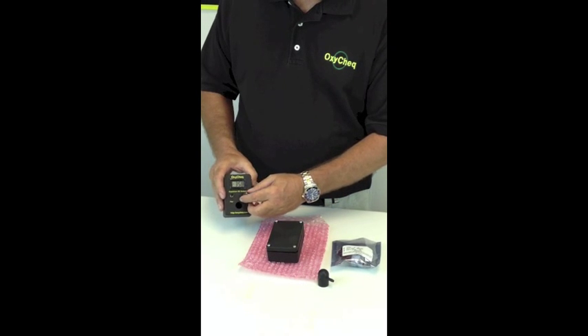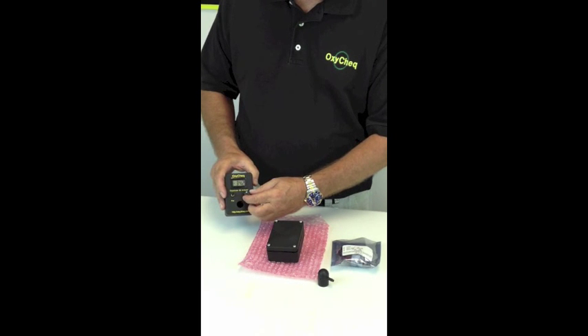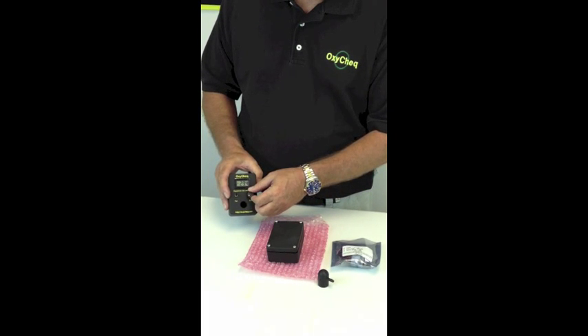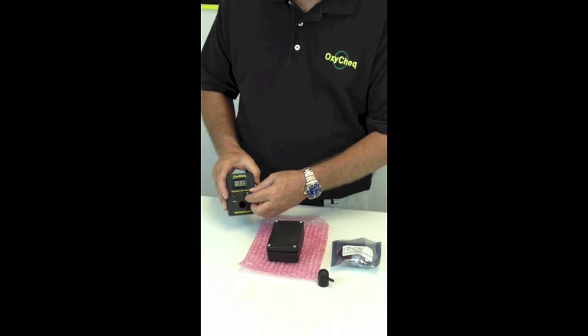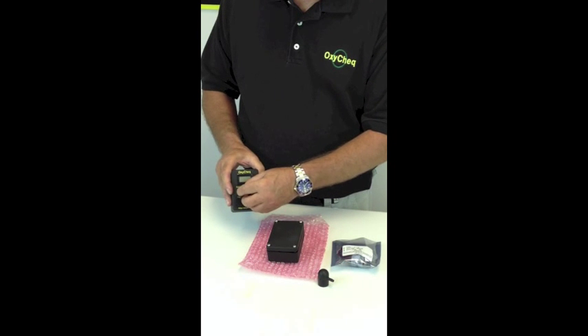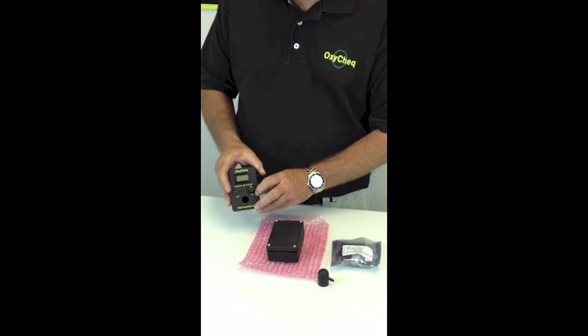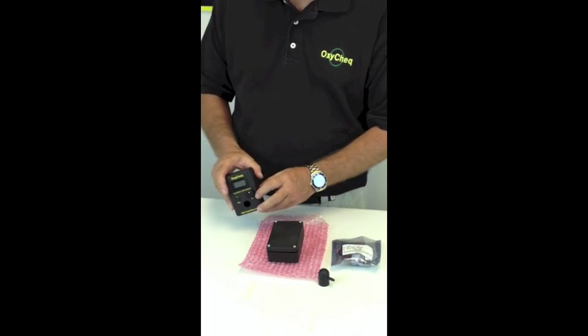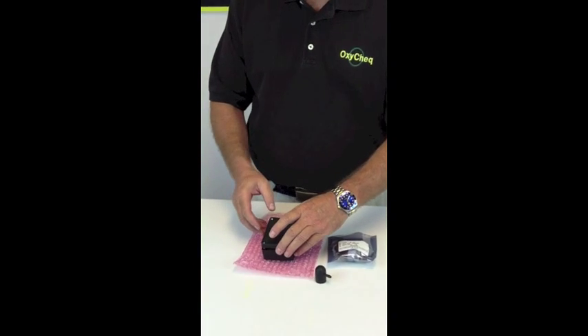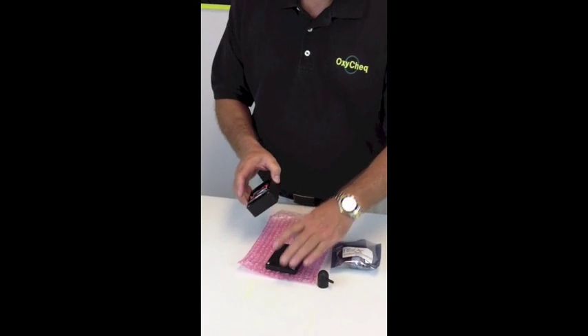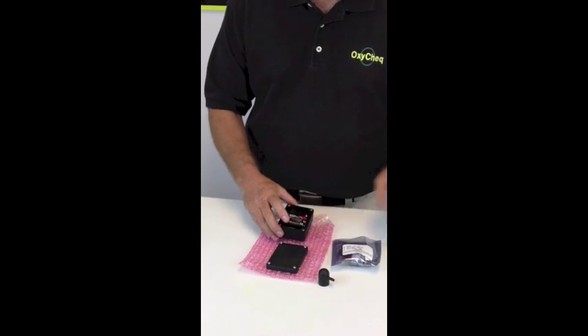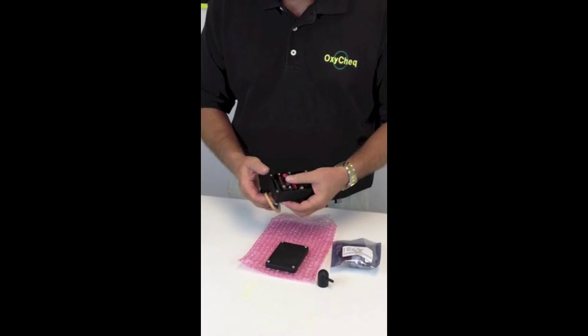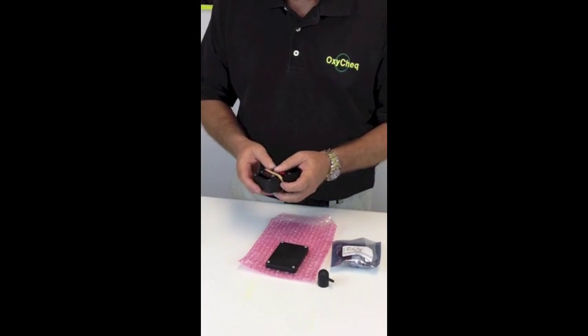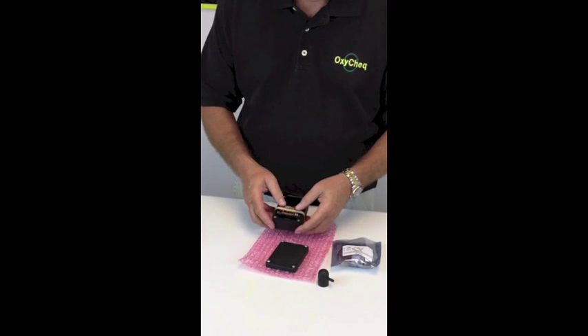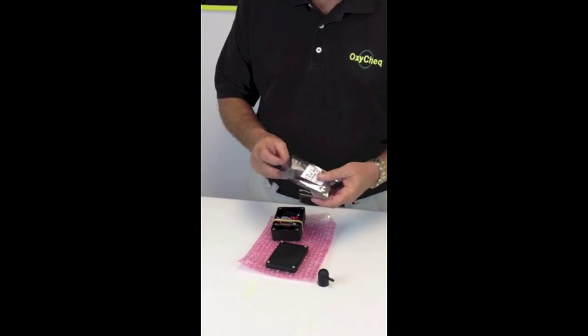Once the backlight is on, we'll take the calibration knob and we'll turn it to the left or counterclockwise. The numbers should go down. If we turn it clockwise, the numbers should go up. Once we verify that it's working properly, turn the on-off switch off, press in the boot to lock it in position. Now we've already got an analyzer that we loosened the screws on just to expedite this session. We take the back of the case off. It's handy to have a rubber band laying around to wrap around the case and the battery pack to prevent it from dropping out. We now take the sensor.